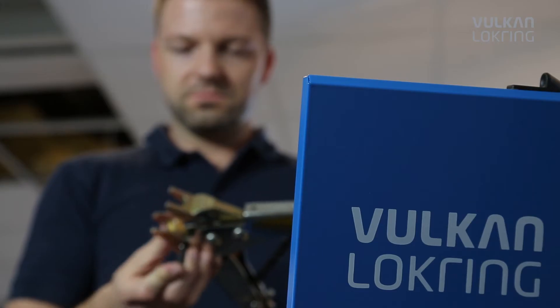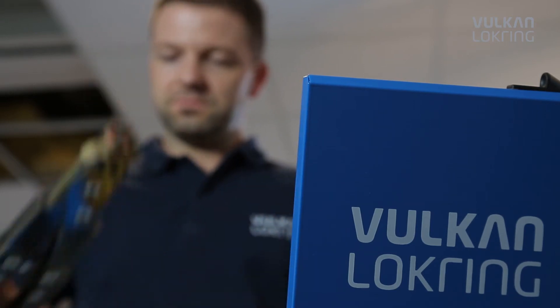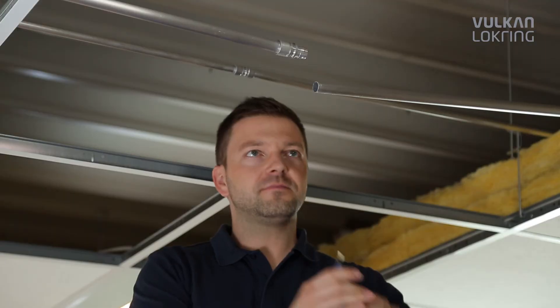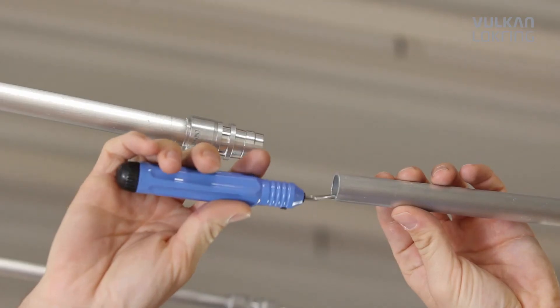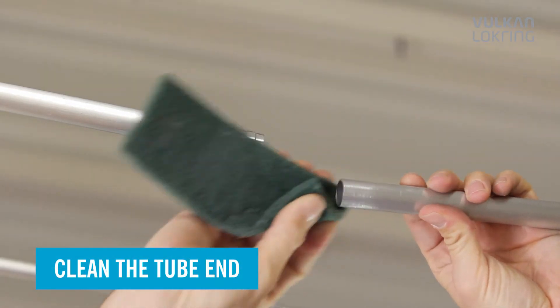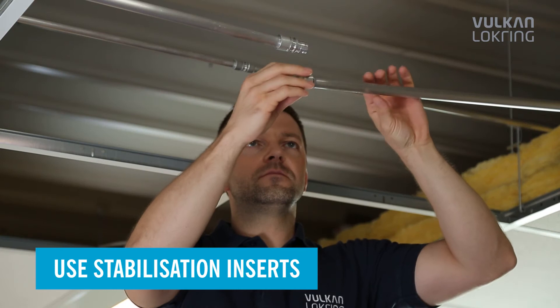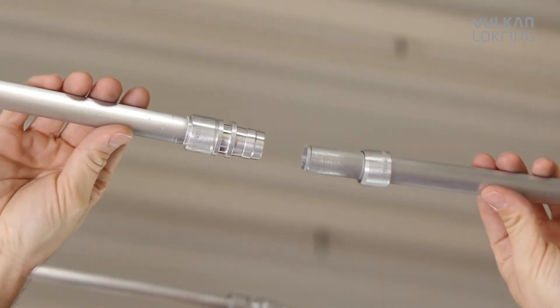So, after only a short time, you're able to apply the Lokring system quickly and reliably. It's this simple. First, deburr the tube and thoroughly clean the tube ends. Use the stabilisation insert to give the connection more stability.